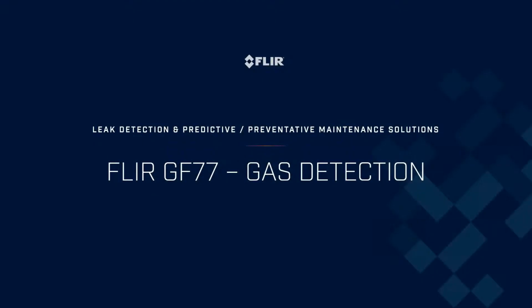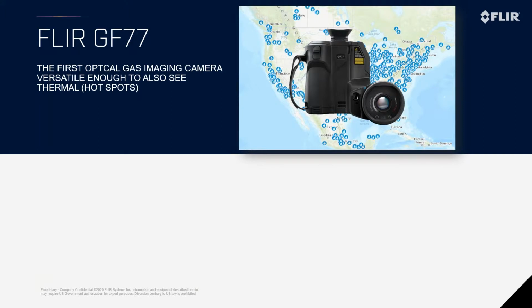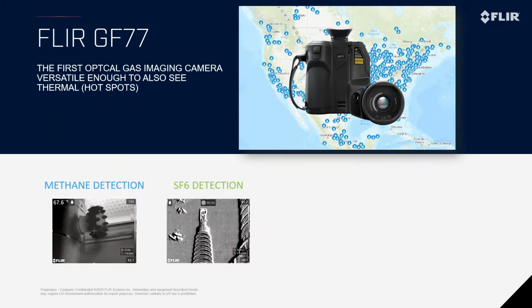So with that, I'd like to introduce our FLIR GF77, Gas Finder 77. This is the first optical gas imaging camera that's versatile enough to also see thermal hotspots. We'll take a look at the different things that this camera can do. And again, this is going to be applicable for many different utility plants and municipalities across the country. The first thing this camera can do is methane detection. Another is SF6 detection, again for those breakers.